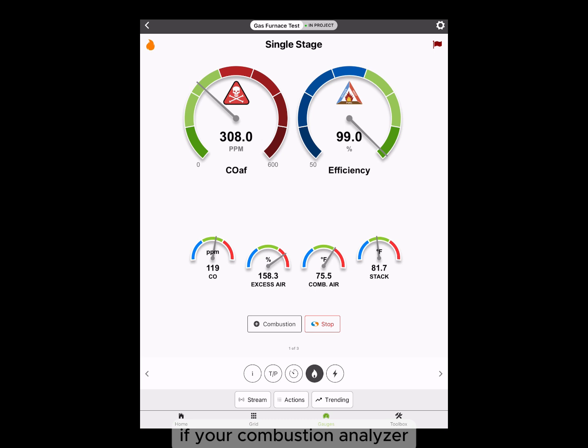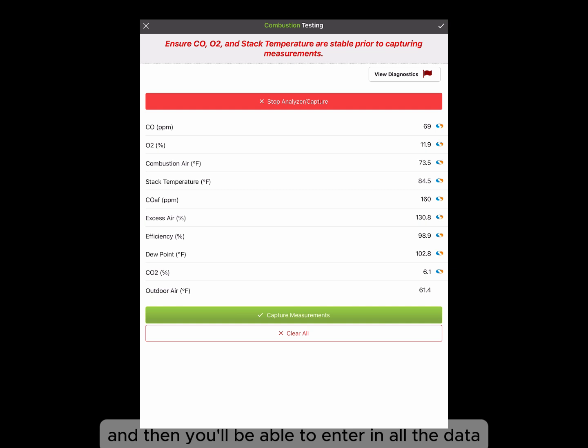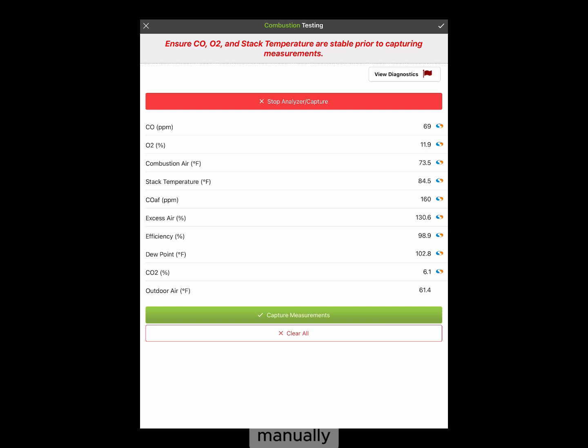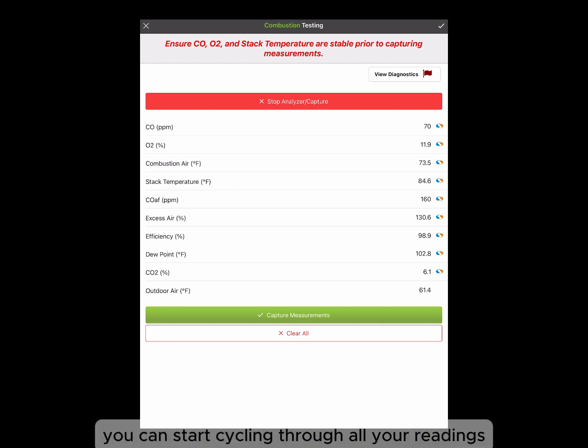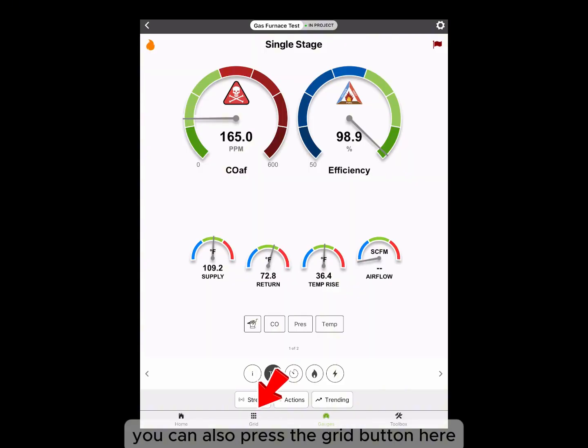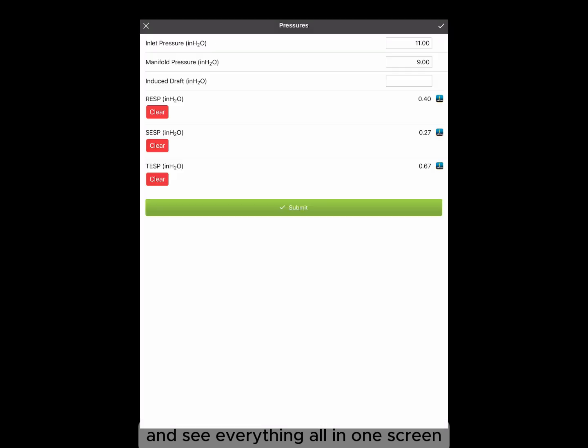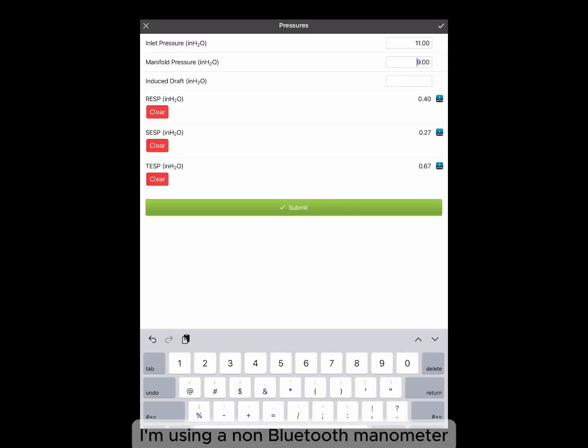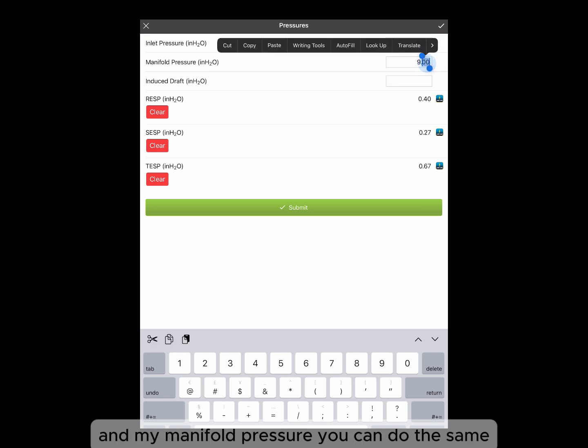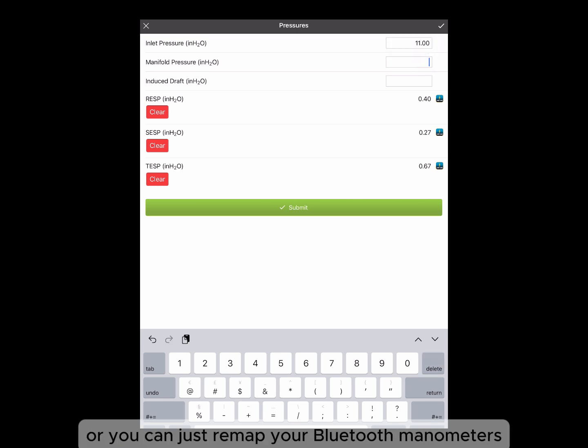If your combustion analyzer does not connect to measureQuick, that's okay. Just hit this flame icon, and then you'll be able to enter in all the data manually. Once you're at steady state, you can start cycling through all your readings and see if there's anything abnormal. You can also press the grid button here and see everything all in one screen. I'm using a non-Bluetooth manometer to check my input gas pressure and my manifold pressure. You can do the same, or you can just remap your Bluetooth manometers.